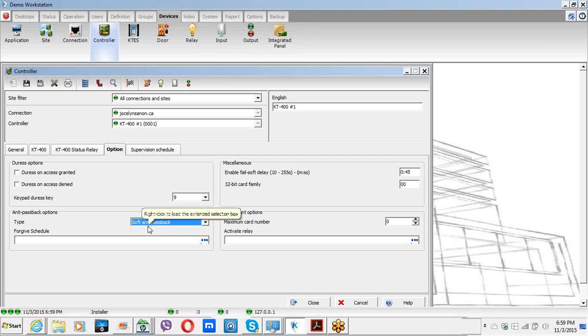Soft anti-passback will generate an alarm if the person is in the wrong passback area. For example, if I enter a building without presenting my card to the reader and then try to leave, I will still be able to leave, but it will send an alarm to the administrator saying 'Jocelyn left but he didn't enter.' With hard anti-passback, if I enter an area without a valid swipe and access granted at the entry, I will not be able to leave, because the system asks how did I get inside in the first place? It will also send an alarm event to the administrator.